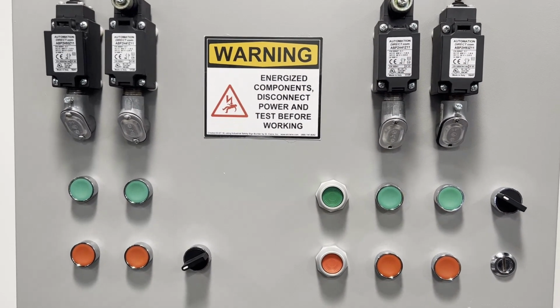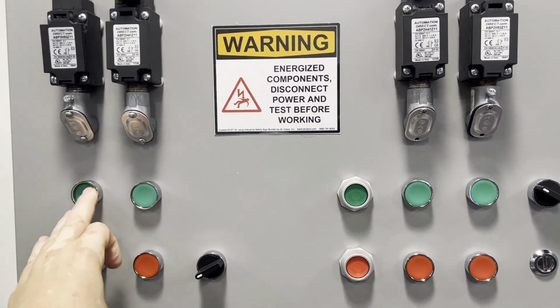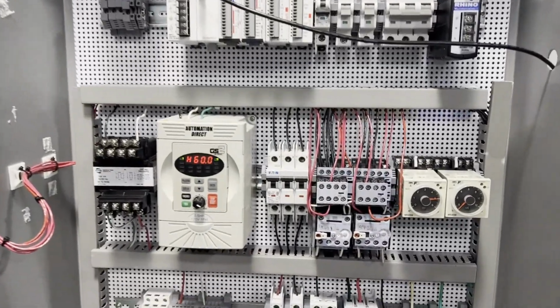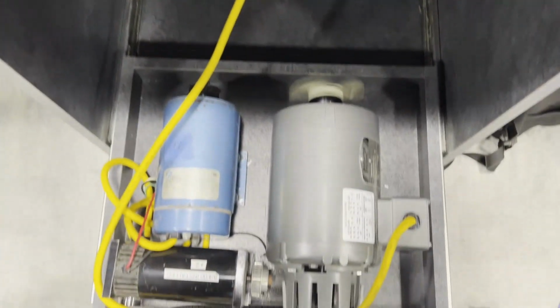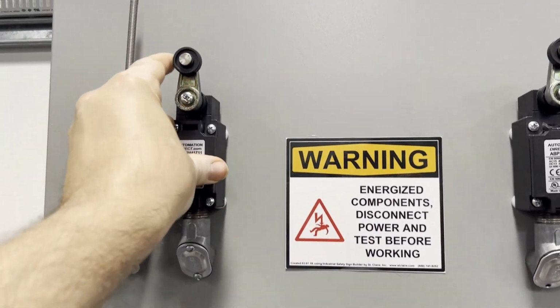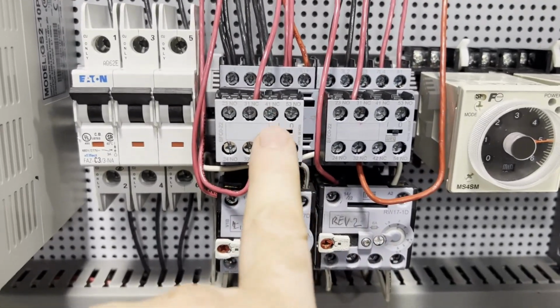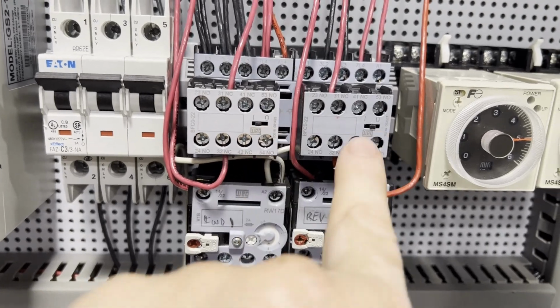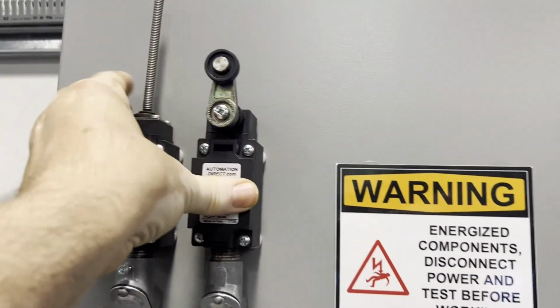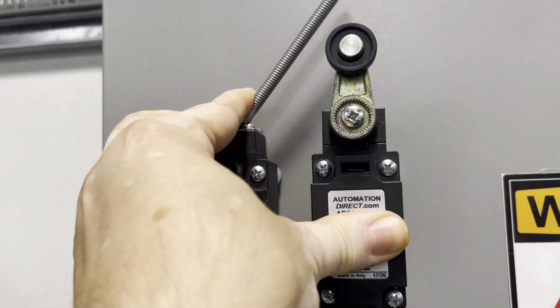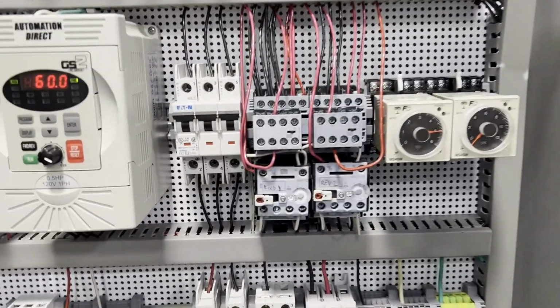Test number 5, forward limit switch. Start out pushing forward. Hear the contactor, hear the motor start. Verify forward contactor closed. Motor running in the forward direction. We push the reverse limit switch. And we still have the forward contactor closed. We're still open. Motor still turning in the forward direction. And now we activate the forward limit switch. Go to sound, verify, forward contactor open, motor coasting down to a stop. This concludes our forward limit switch test.